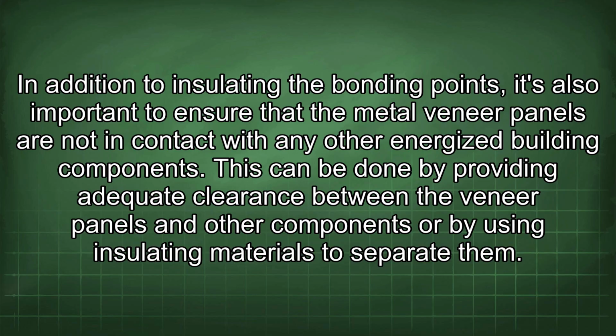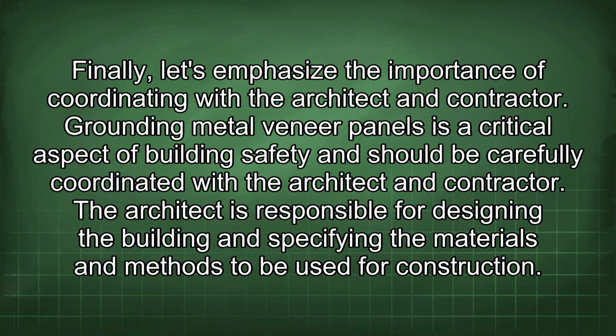In addition to insulating the bonding points, it's also important to ensure that the metal veneer panels are not in contact with any other energized building components. This can be done by providing adequate clearance between the veneer panels and other components, or by using insulating materials to separate them. Finally, let's emphasize the importance of coordinating with the architect and contractor. Grounding metal veneer panels is a critical aspect of building safety and should be carefully coordinated with the architect and contractor. The architect is responsible for designing the building and specifying the materials and methods to be used for construction.